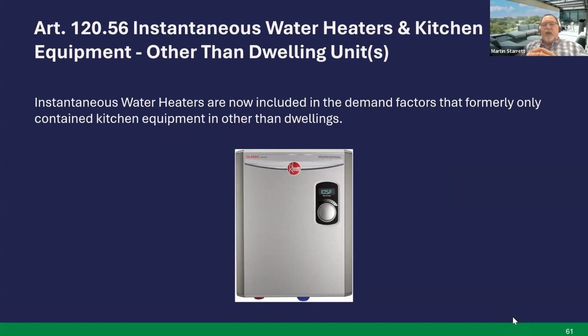Instantaneous water heaters and kitchen equipment other than dwelling units. Now instantaneous water heaters are included in the demand factors that formerly only contained kitchen equipment in other than dwellings. By this addition, these InstaHots that are installed in these kitchens can now use the demand factors that the kitchen equipment was using. It helps whenever they install these in the kitchens, because now they'll be able to use those same demand factors whenever they're figuring load calculations. Next slide.